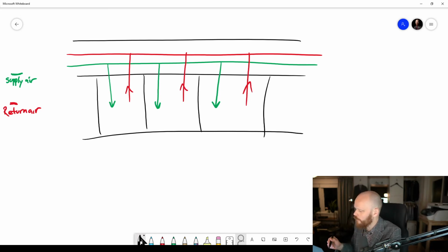Now this one is a lot better with regards to sound, because first, we no longer need to go through this wall. Typically the sound requirements here are higher than the sound requirements here, and that means the pass-through here is a bit more forgiving. The reason you have lower sound requirements towards a corridor is that here you have doors, and when you have doors you typically get by default a lower sound insulation class, because a door cannot be as strong as the wall with regards to sound insulation.